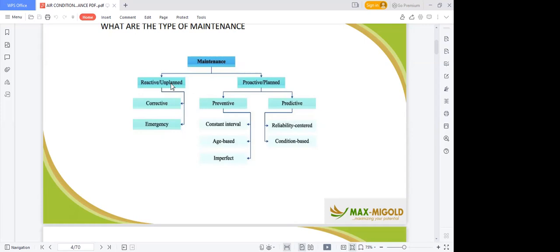The filters must be cleaned. The outdoor unit must be pressure washed to remove dust that can hinder the cooling of the equipment. Then you check your electrical cables, check your copper pipe, check your insulation, check the electrical power rating into the unit, and check that everything is fine, because it can actually disappoint also. Then the unplanned one is the same thing, that you are not planning at all. You go into some building, you ask them, sir, when last did you maintain your AC? They tell you, I can't remember. They don't have a planned program for their HVAC.